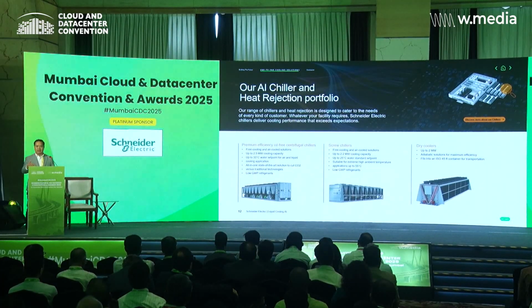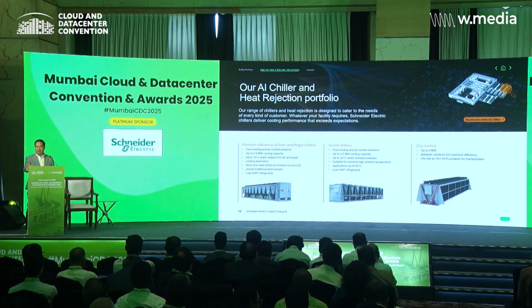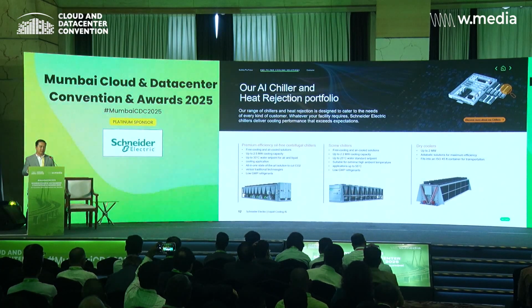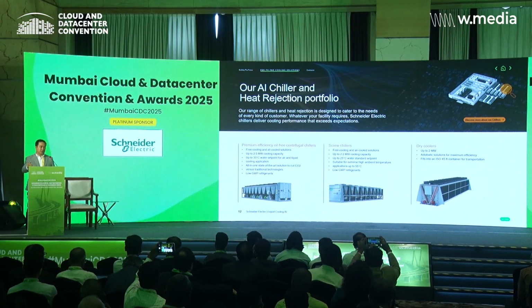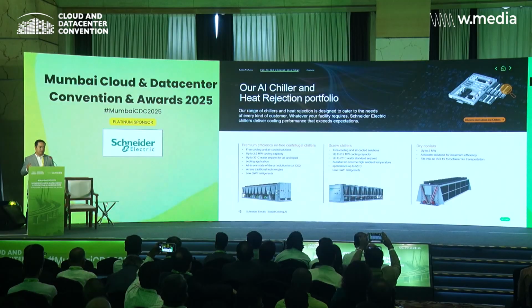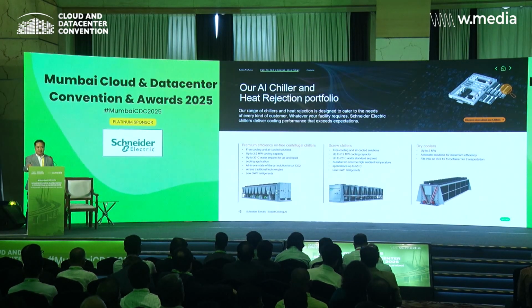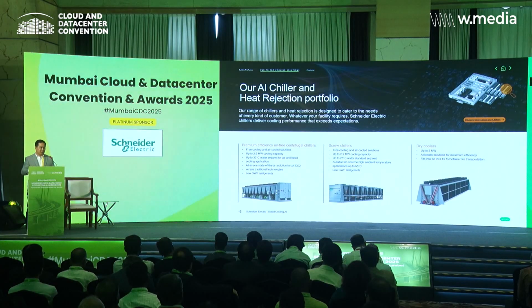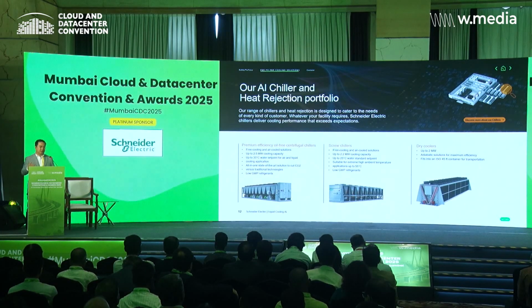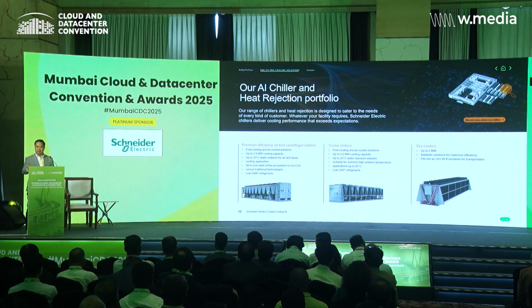At the end, the biggest power consumption in a cooling system is really the heat rejection or refrigeration cycle. There are instances where we can use free cooling, but in certain environments, like Mumbai, it's very difficult to achieve that without leveraging adiabatic or water usage.